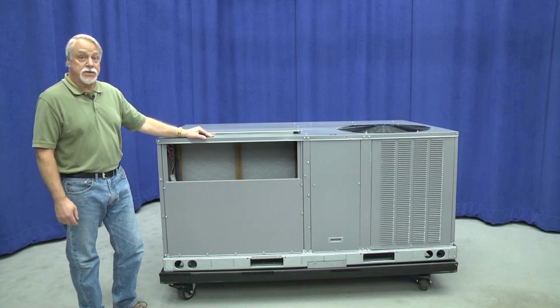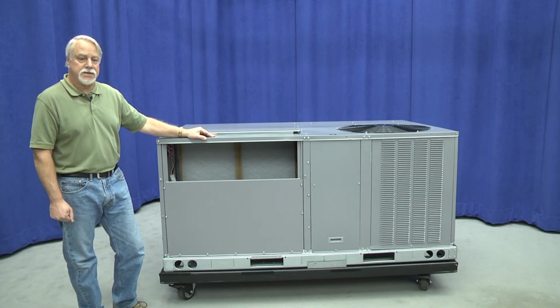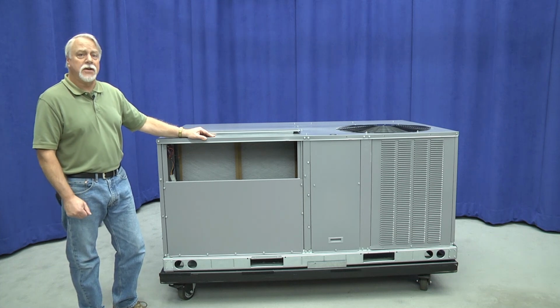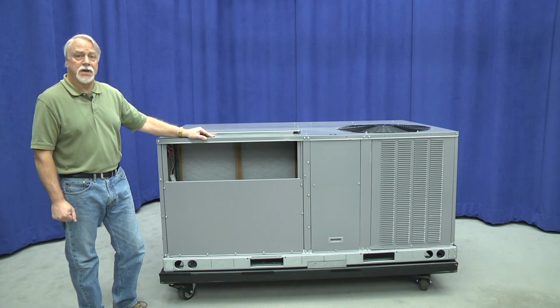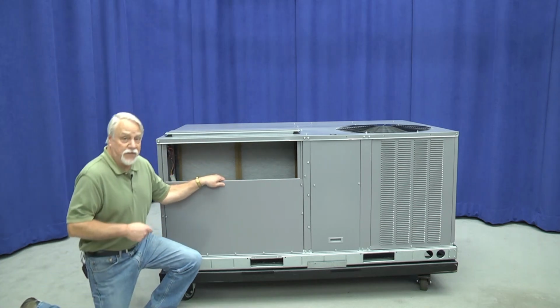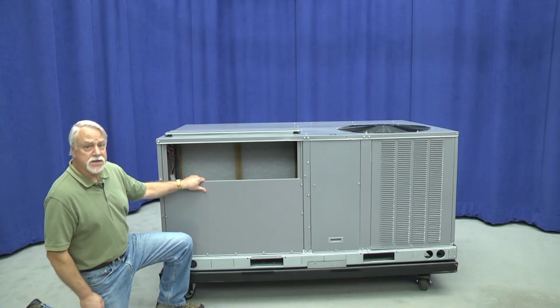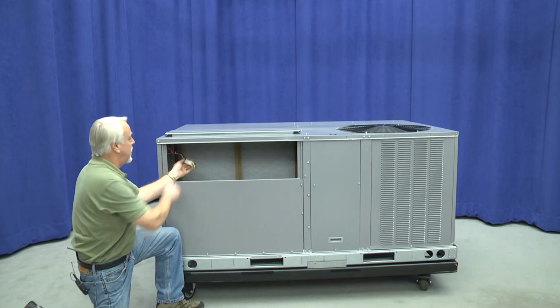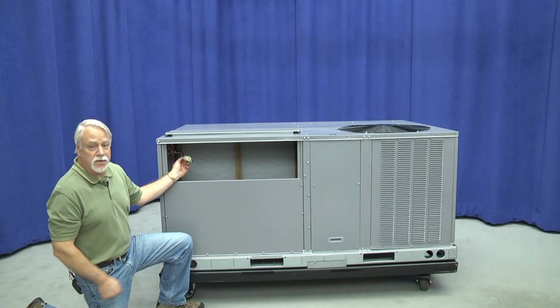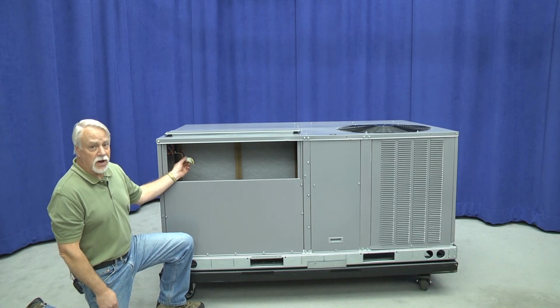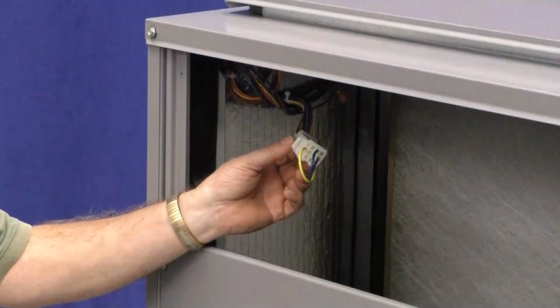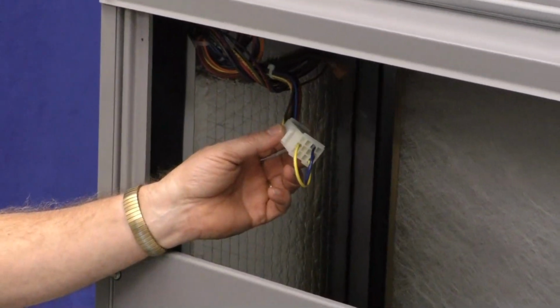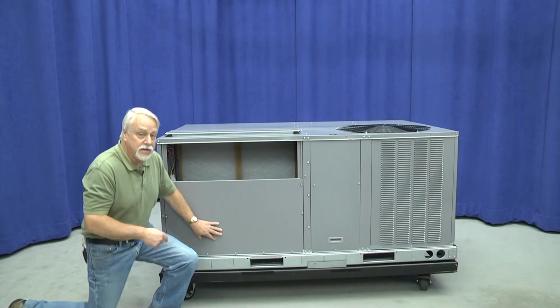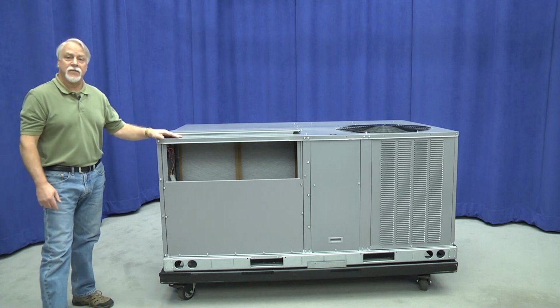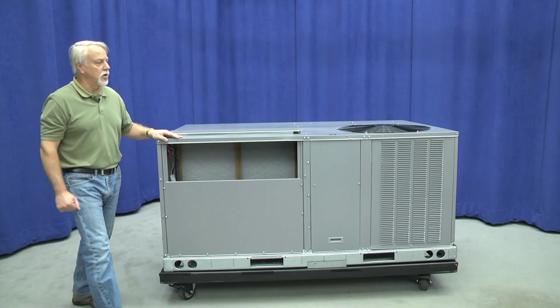Economizer options and accessories, which are very popular with this particular chassis size, have not changed. The many different types and styles of economizers that are available with the current product will fit this particular product. Access is the same. As a matter of fact, the connection for the wiring harness to interface with those economizers once they're installed is still here also. So if you've got an economizer as an accessory field installed or as an option from the factory, this is the connection point and this is the mounting point. This panel is the same, as well as the opening in the bottom for the return air. So it fits on the same curb.